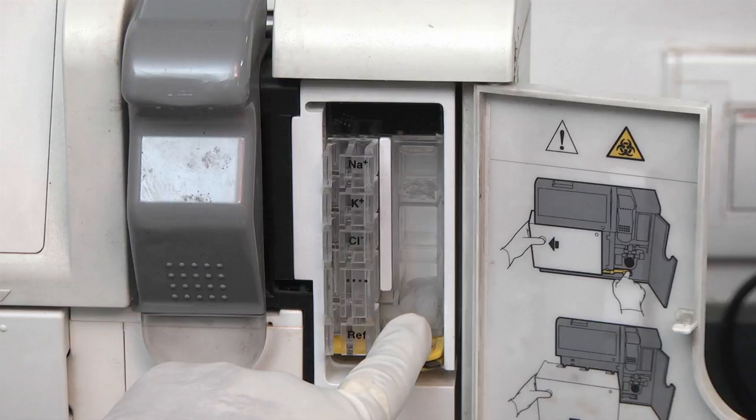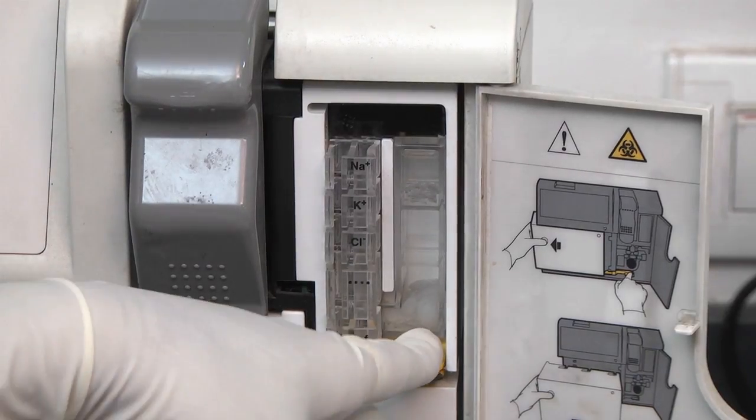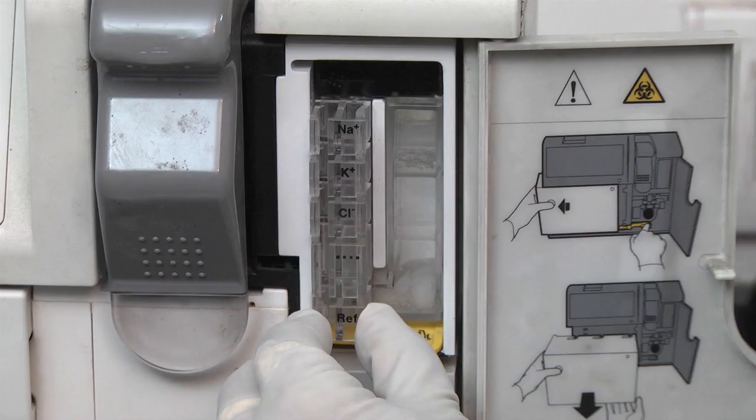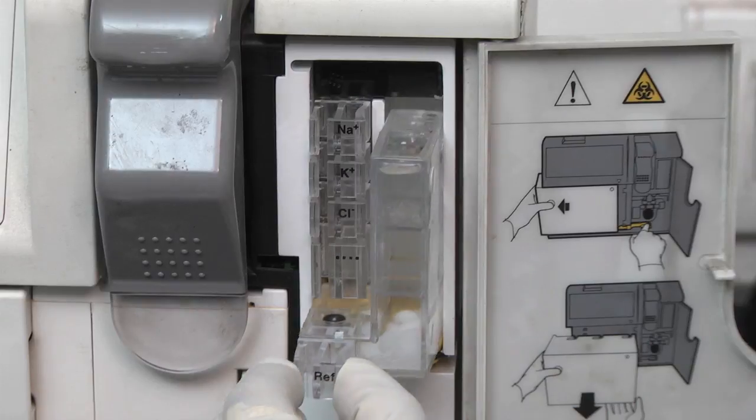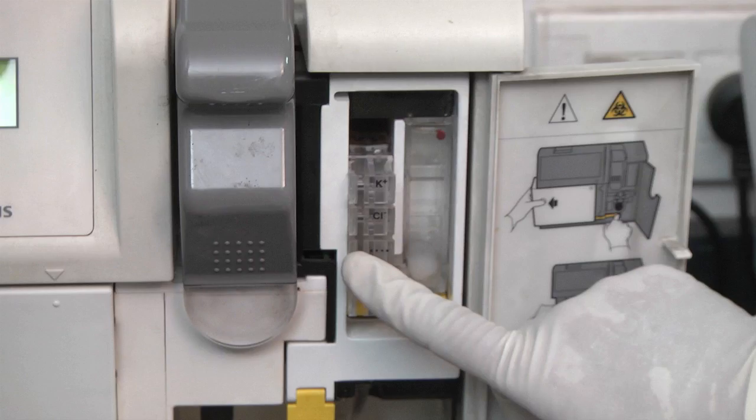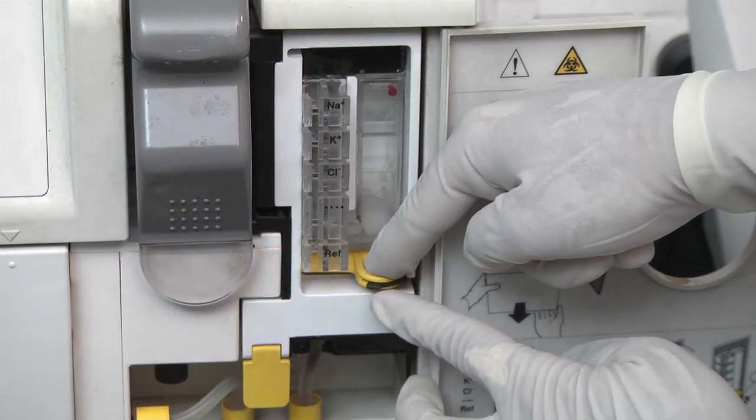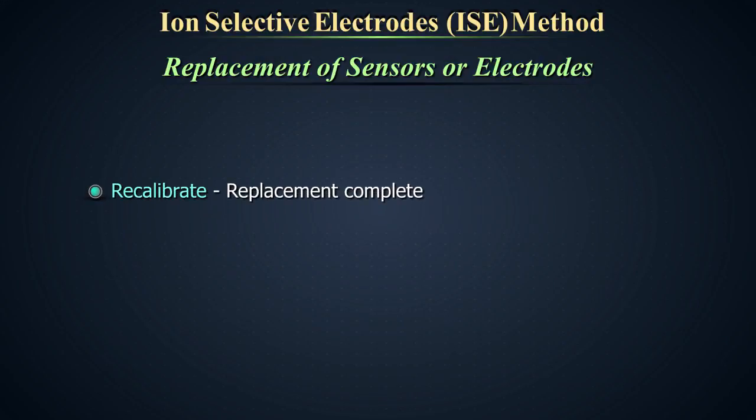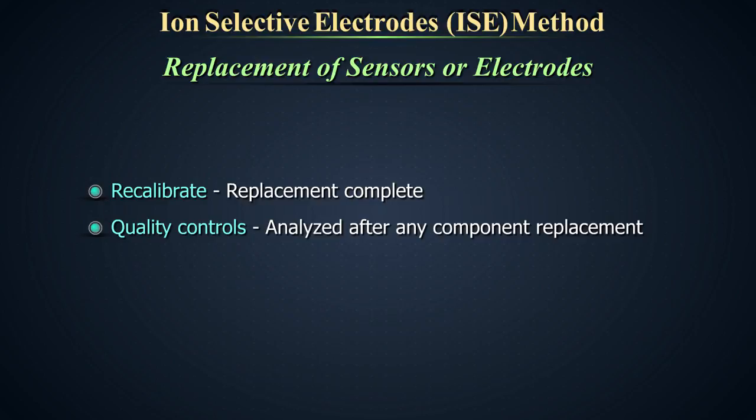To remove a sensor, push the compression plate down until the latch locks into the open position. Grip the desired sensor handle, squeeze and pull it straight out from the sensor module. To install a new sensor, push the sensor gently into its designated slot till the handle snaps into the sensor module. Do not force. Recalibrate when replacement is complete. Quality controls should be analyzed after any component replacement.